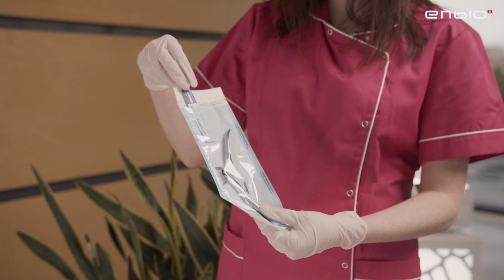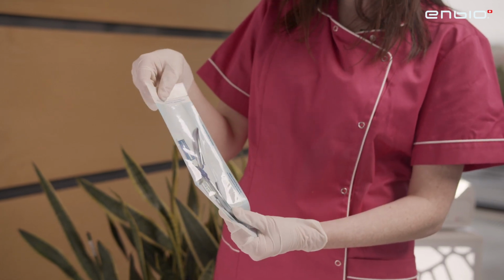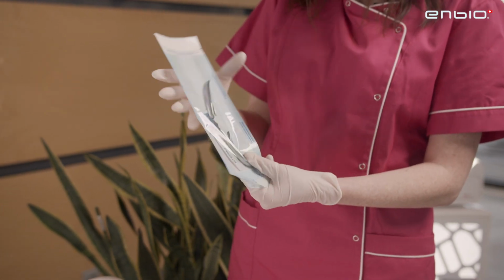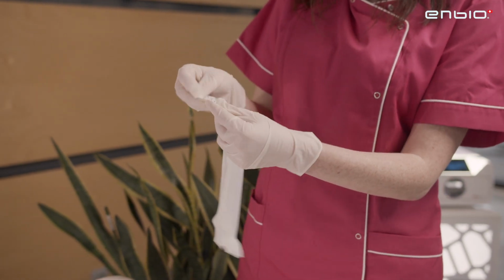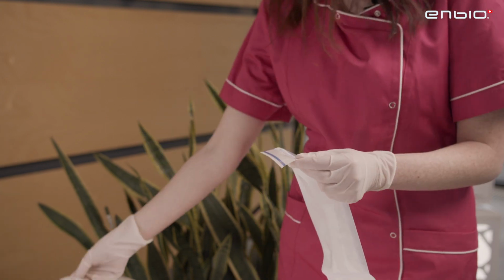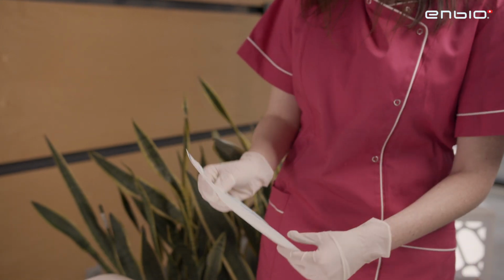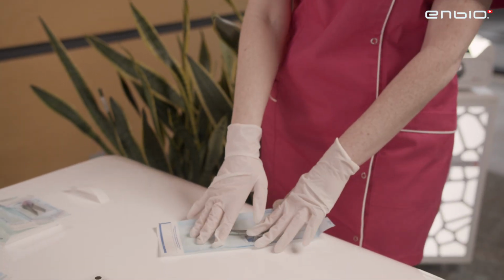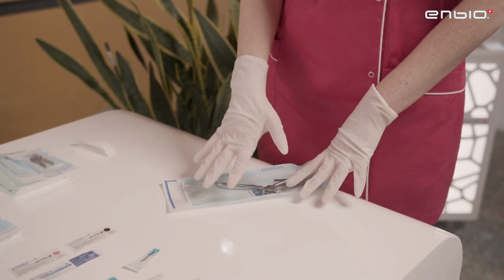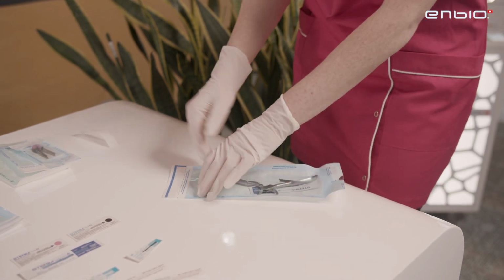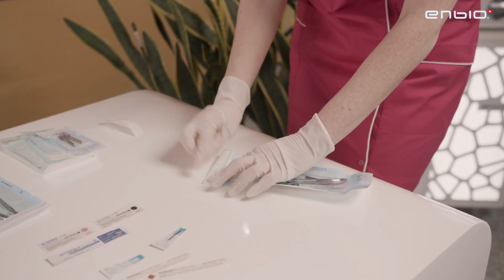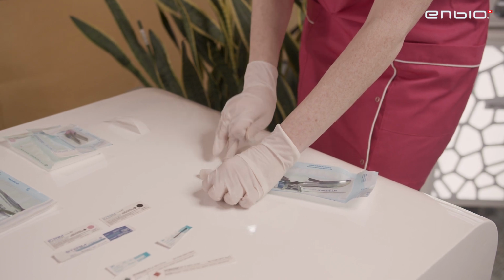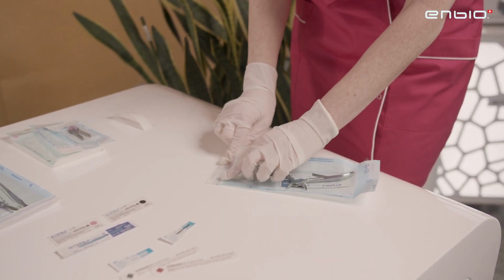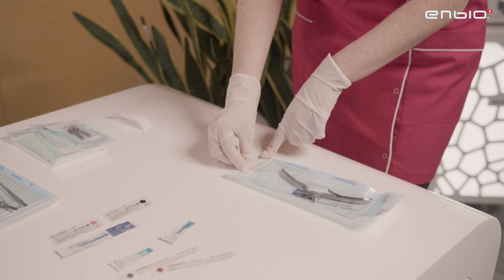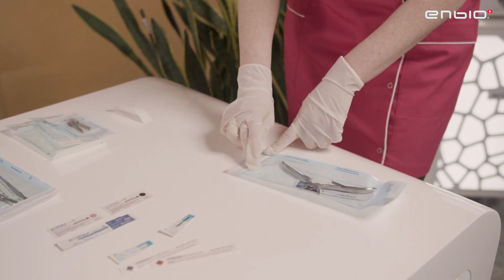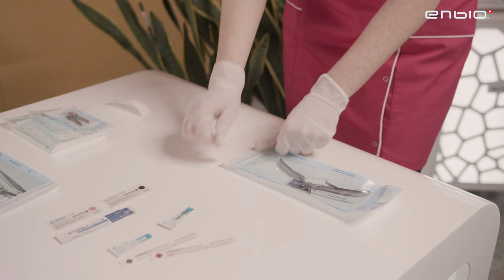So I'm going to introduce the chemical indicator that proves the efficiency of the sterilization process, and then I'm ready to seal the sterilization pouch. I'm going to remove this part here. And when we try to seal the sterilization pouch, it is important to have the pouch on a perfectly plain and hard surface so that we seal it perfectly. We have to make sure that on this portion here, the air is not penetrating.